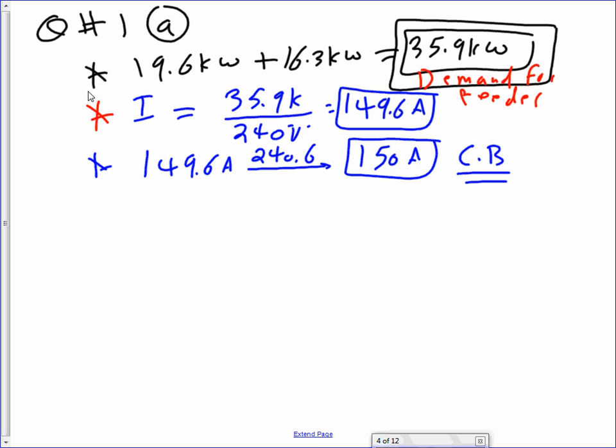Then you take the 150 amps to table 310.15(B)(7). Can you guys go to 310.15(B)(7) and find me the feeder? Why B7? Because we're still doing dwellings. We don't want to go to 310.16. So 150 will give me, what's the size?